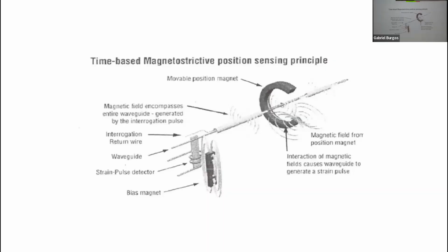That twitch sends back a mechanical pulse, which is what this thing here detects. It looks at that mechanical pulse, and the electronics measure the time from when you started the pulse to when you get the twitch back. Since you have a constant sound speed, bingo, you can figure out where that magnet is. And there's literally, except for mechanical considerations, no limit on how long the wire could be.